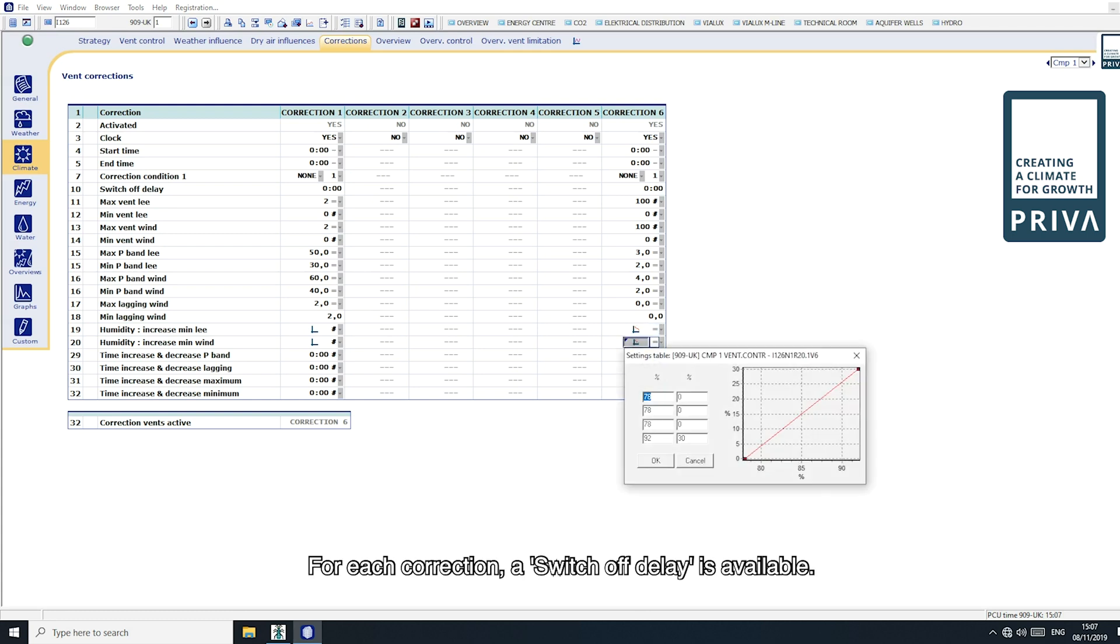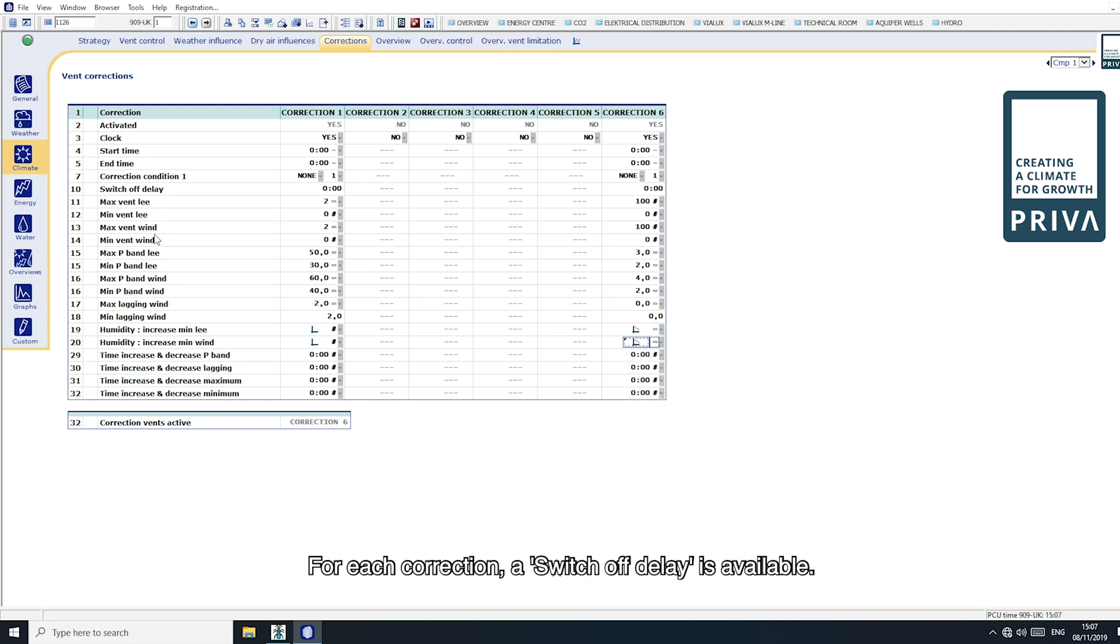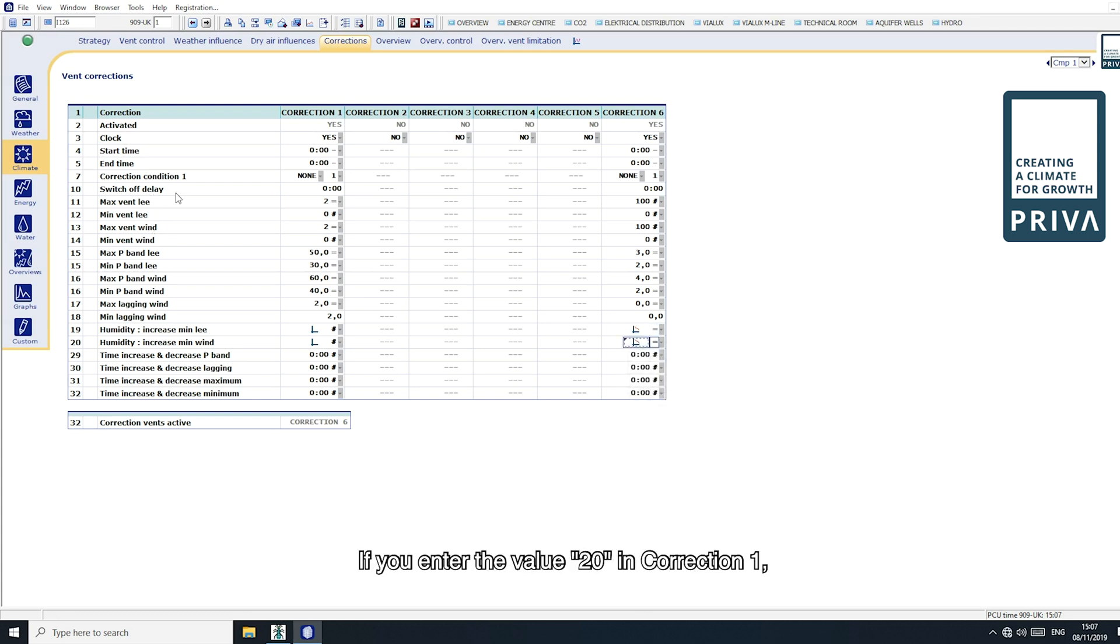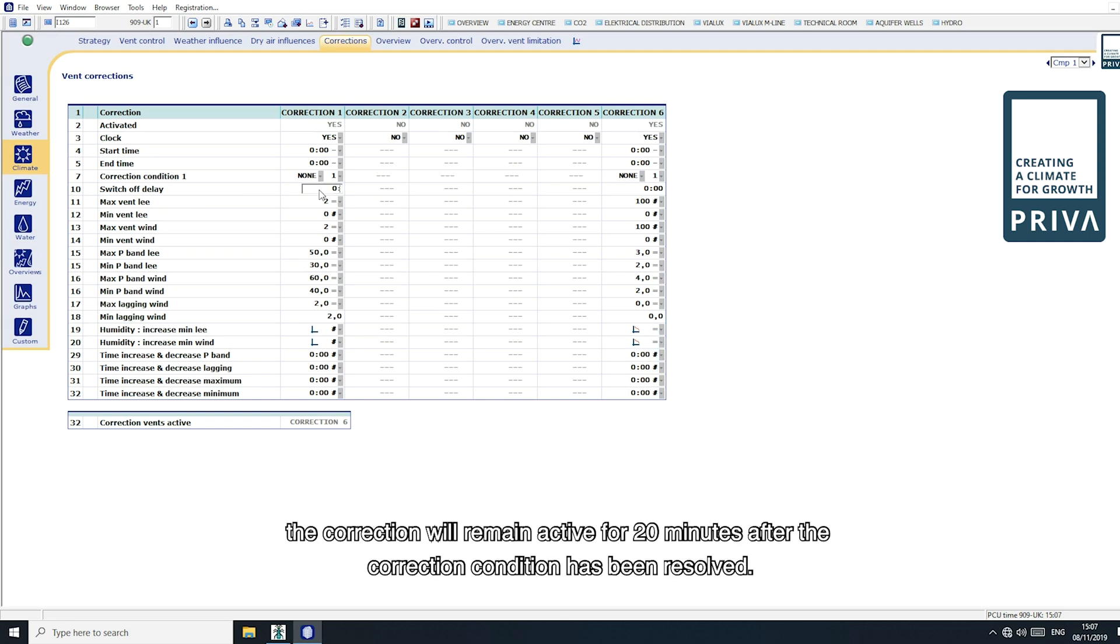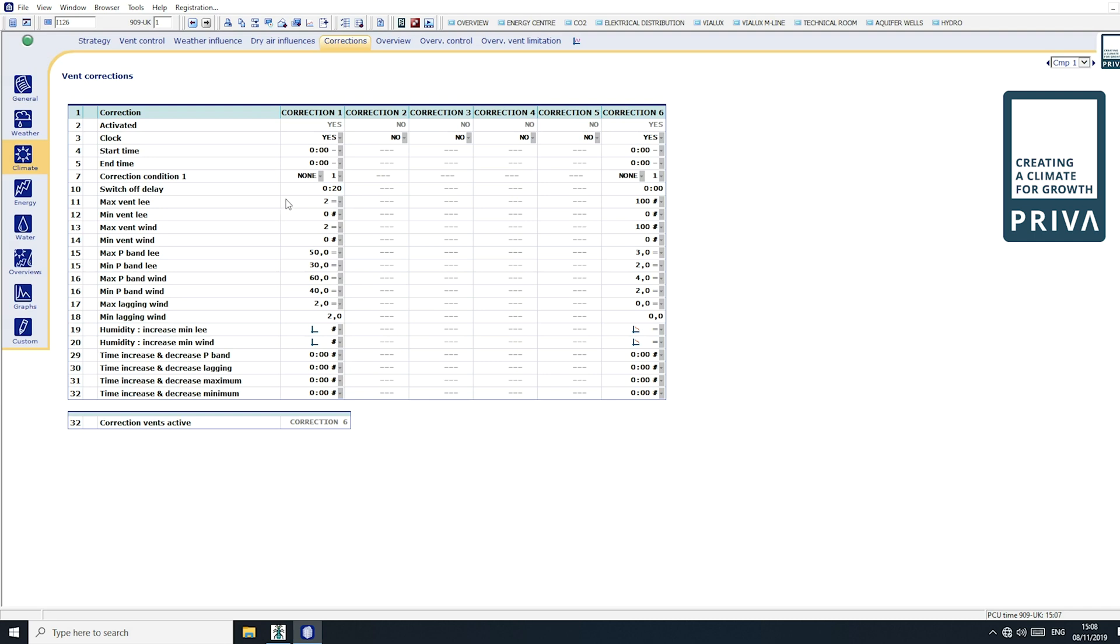For each correction a switch off delay is available. If you enter the value 20 in correction 1, the correction will remain active for 20 minutes after the correction condition has been resolved.